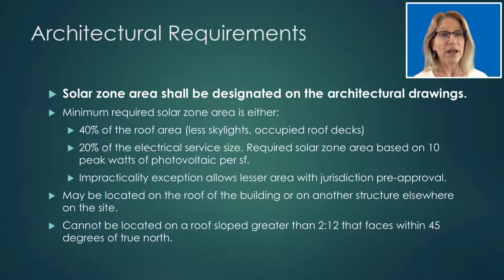And the required solar zone area based on electrical service size is based on 10 peak watts of photovoltaic per square foot. Now, there is an impracticality exception, and I'll just read that exception so that everybody's clear what it says. It says, subject to the approval of the code official, buildings with extensive rooftop equipment that would make full compliance with this section impractical shall be permitted to reduce the size of the solar zone required to the maximum practicable area. So the gist of this is that this exception is not so that a project doesn't have to comply with this provision at all. All it's saying is that if there are obstacles to meeting the required percentage of designated roof area, the designer can coordinate with the jurisdiction and figure out what would be a practical area that could be required to accommodate a future solar system.